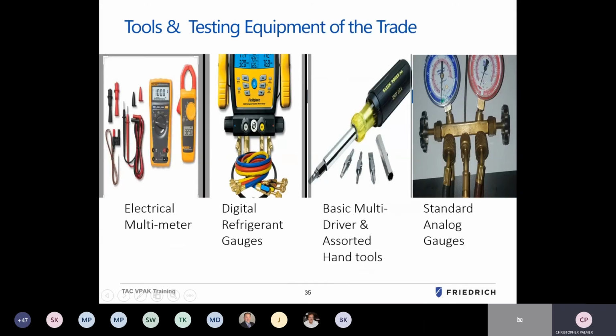Some basic tools that I always recommend having on hand to do the troubleshooting that we require. Oftentimes we'll ask for voltage readings, ohms readings, sensor readings, supply voltage readings. It's good to have a good quality multimeter. Not brand specific here to the image, but a clamp meter, test leads, etc. Digital refrigerant gauges are also a professional choice. Standard analog gauges basically get the same pressure readings done without all the bells and whistles. And then your basic hand tools are oftentimes good to have on hand when troubleshooting equipment.